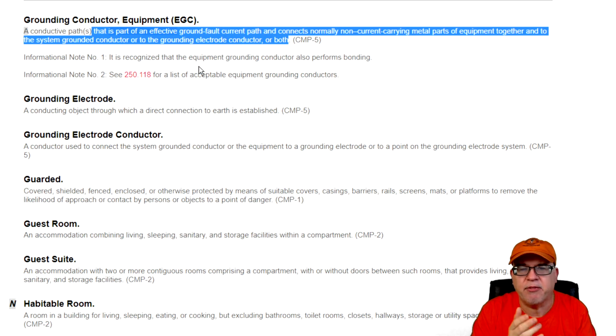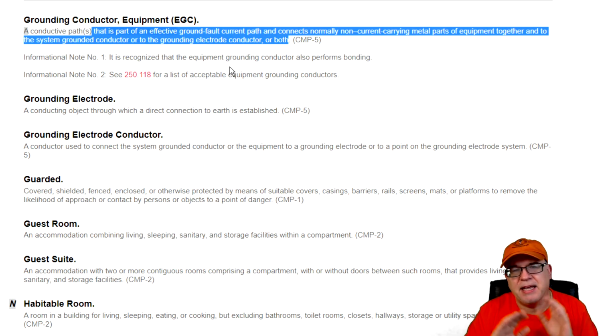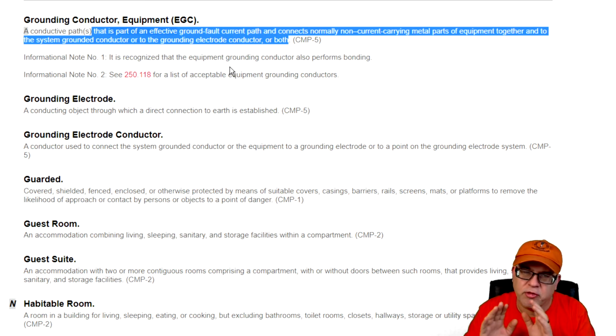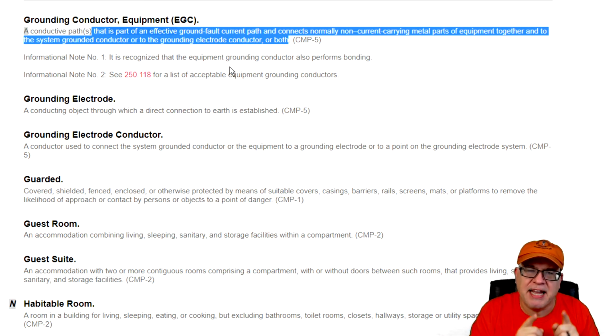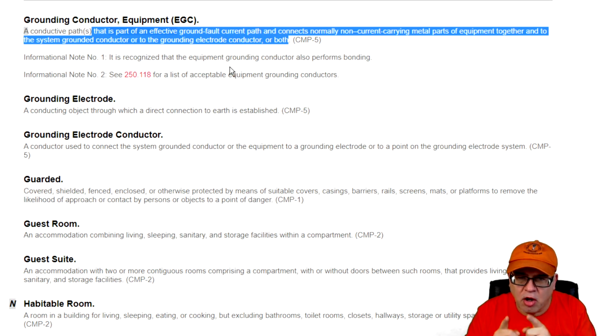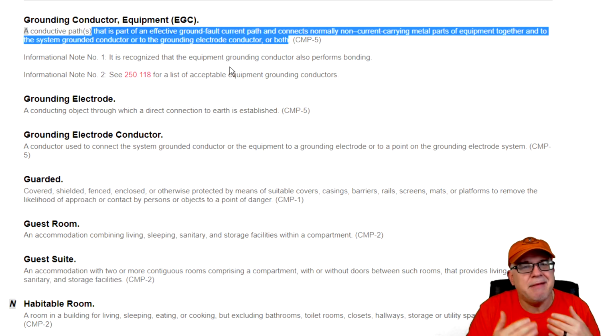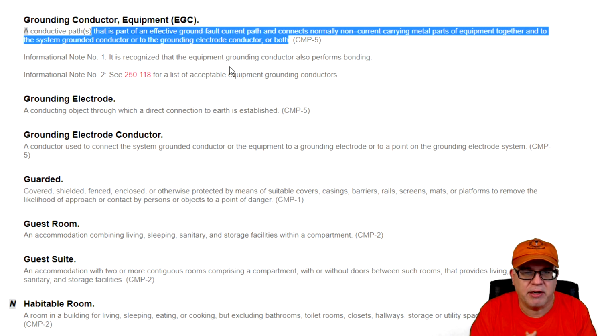And the good news here is we have informational notes. And the first informational note says, hey, it is recognized that the equipment grounding conductor also does bonding. Again, that's to make people feel happy when they're trying to change it to equipment bonding conductor. Okay? Because it ultimately makes connection to the grounding conductor, which makes connection to earth, it's more justified to be called equipment grounding conductor, okay? Because it's also stabilizing the voltage all the way through the system. So it makes more sense to keep an equipment grounding conductor. And it does serve a bonding function. So again, just to clear.